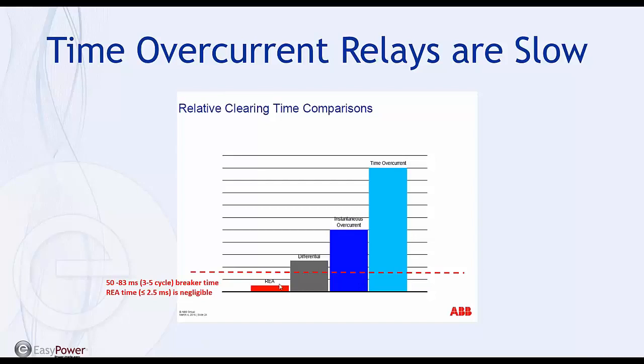You can see here that I drew kind of an arbitrary danger line, say 100 milliseconds. Your REA operates below that, whether it's a 3 or 5 cycle breaker. It operates fast enough to where you're going to avoid damage even at those high arcing currents. The differential is extremely fast, but you can still have a little bit of damage, instantaneous even more so. And time over current is really, to me, not an acceptable arc flash solution. You're going to have considerable damage and jeopardize personnel safety. So there's the relative difference in speeds. Obviously the REA arc flash system, or any arc flash system, is the way to go.